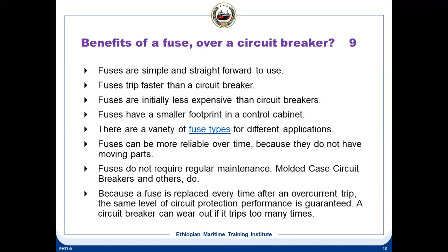Fuses can be more reliable over time because they do not have moving parts. That's the main important point. If there are no moving parts, it is more reliable. It doesn't require maintenance. And it is replaced every time after an overcurrent trip, so the same level of circuit protection performance is guaranteed.